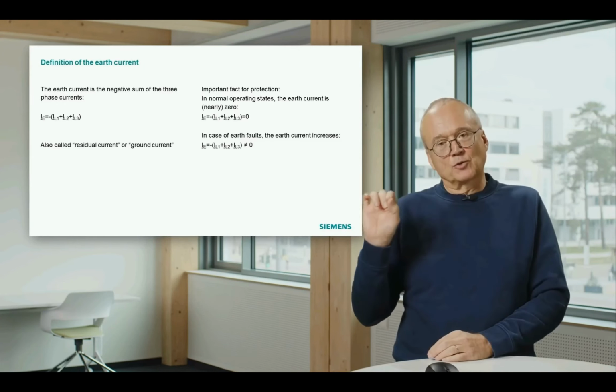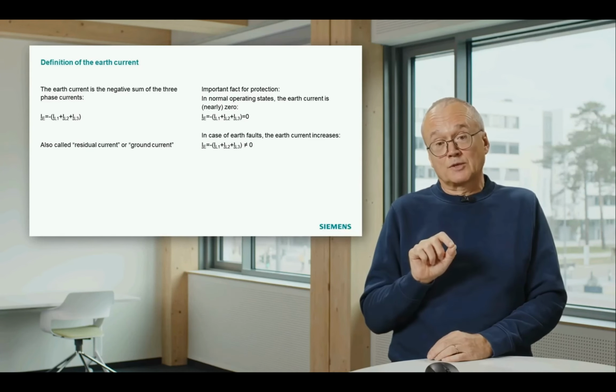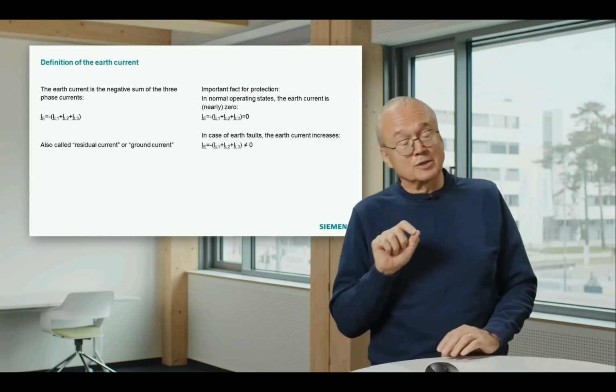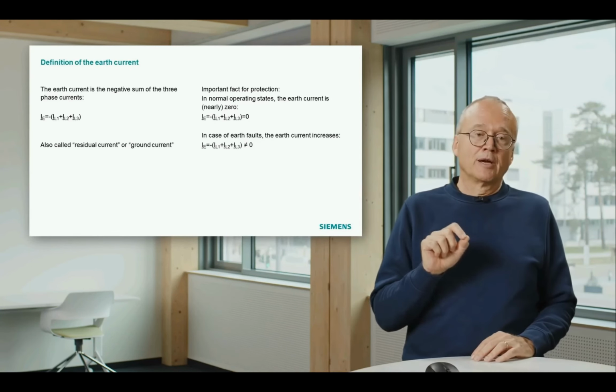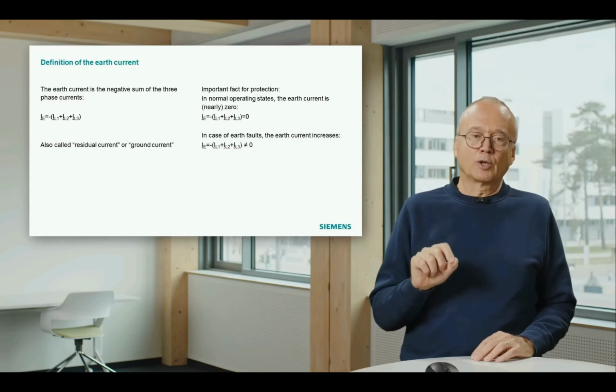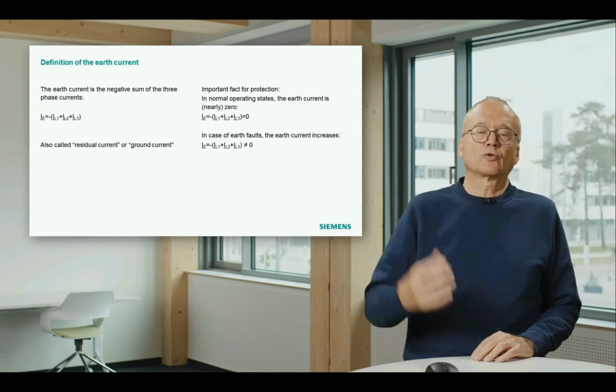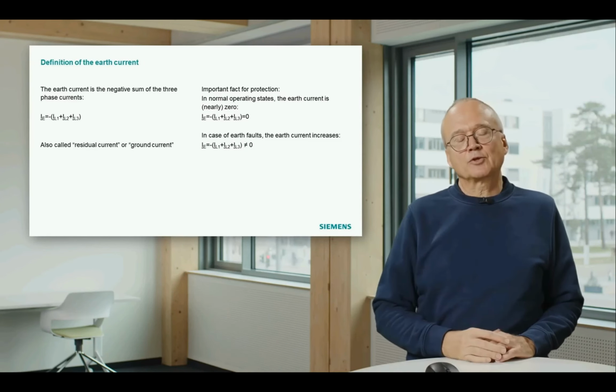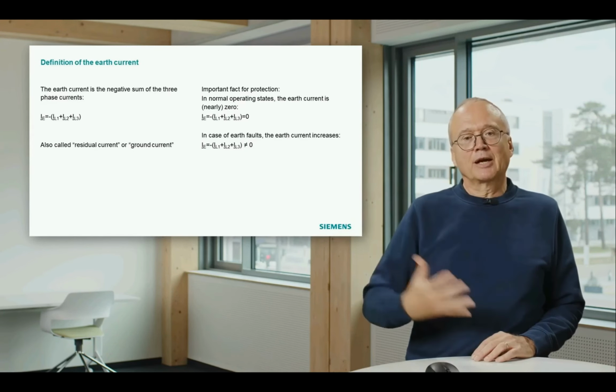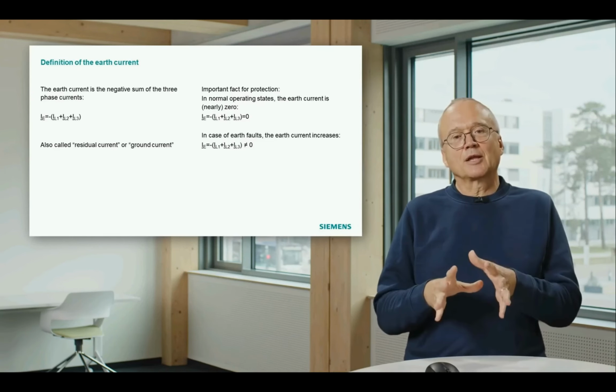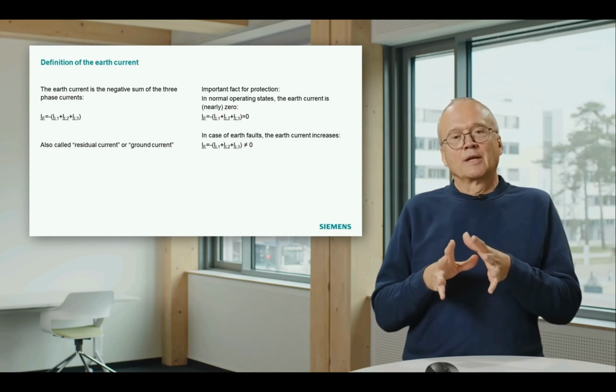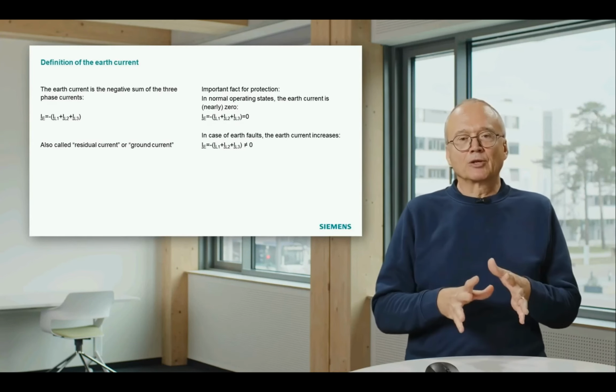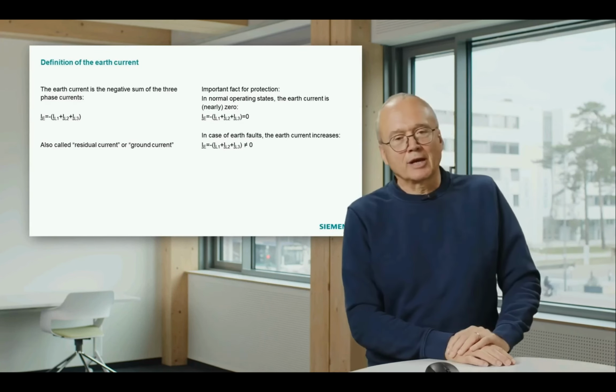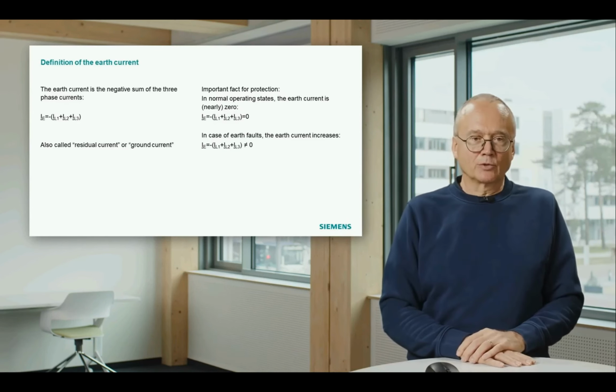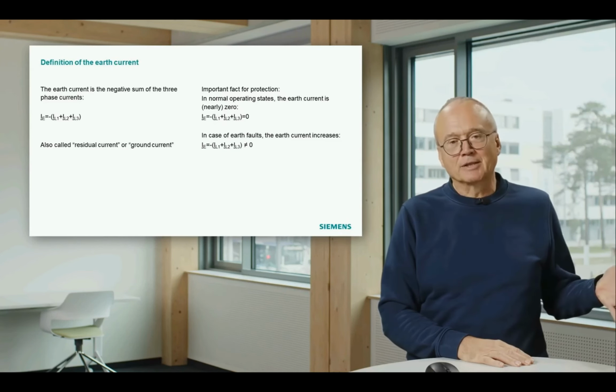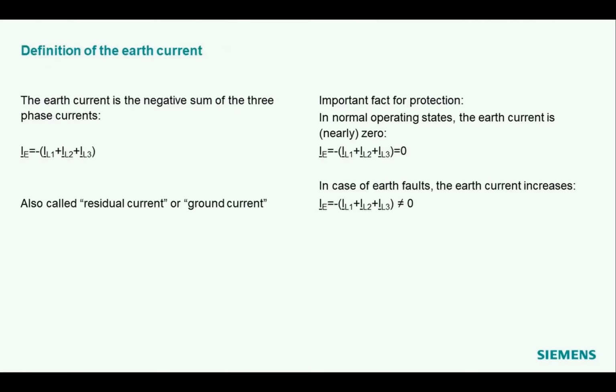And always remember, phase to ground faults are the majority of the faults. And phase to ground faults are also those faults which tend to have higher fault resistances. Now, imagine a tree falls into a distribution overhead line. You can have pretty high fault resistances. That means these are the cases where the fault currents can be pretty low, and it makes sense to have a better opportunity to detect them than we had up to now when we only looked at the phase currents.